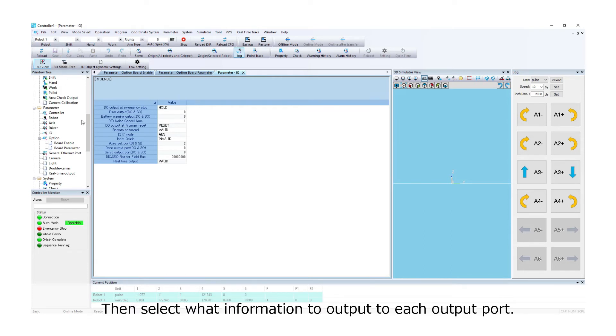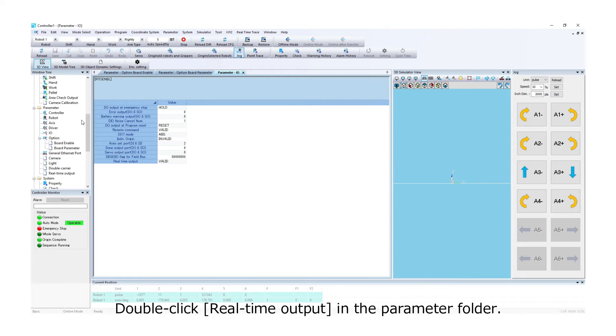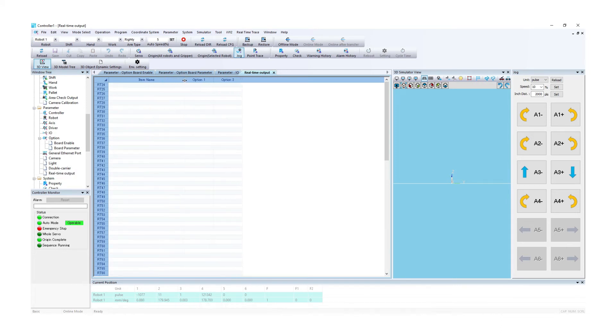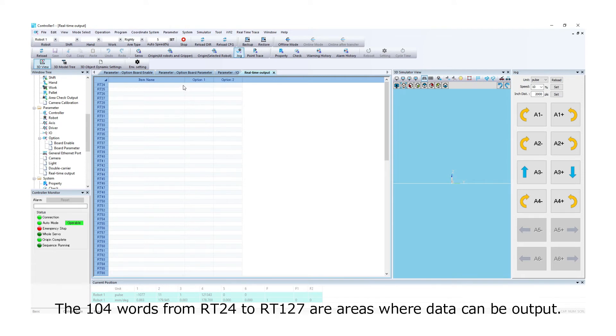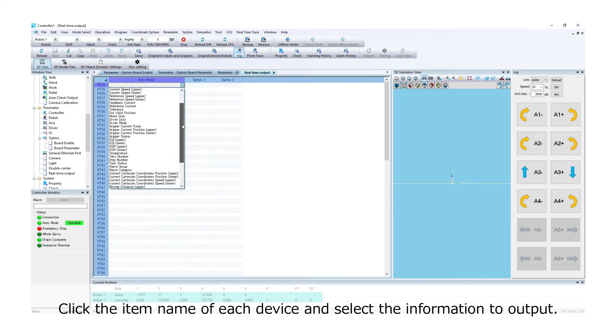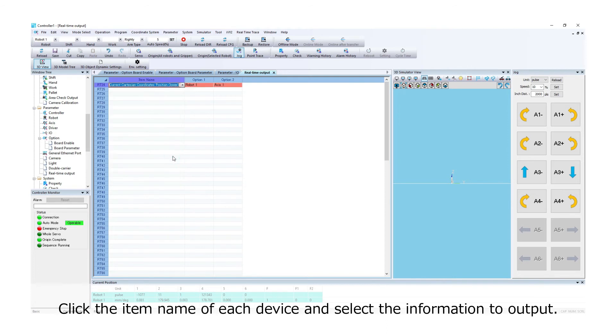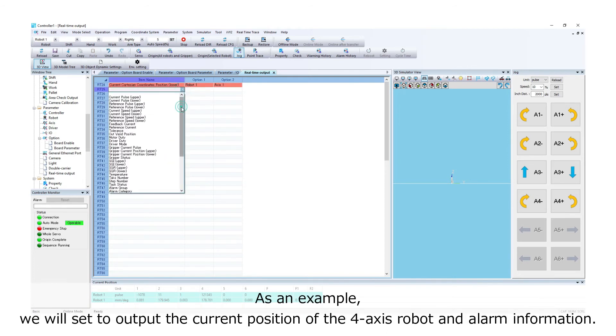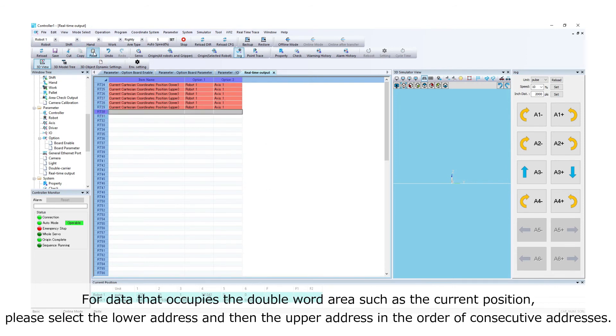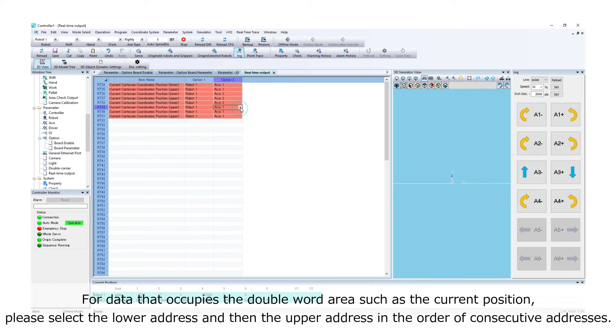Select what information to output to each output port. Double-click Real-time output in the parameter folder. The 104 words from RT24 to RT127 are areas where data can be output. Click the item name of each device and select the information to output. For data that occupies the double-word area, such as the current position, please select the lower address and then the upper address in the order of consecutive addresses.